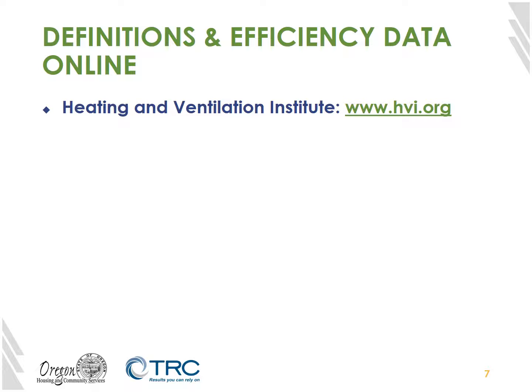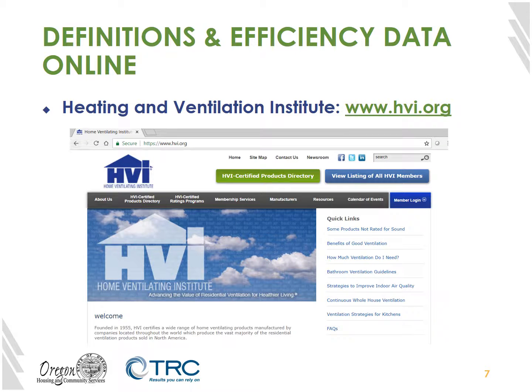We can look at some more definitions and some efficiency data online. The Home Ventilating Institute, also known as HVI, can be found at www.hvi.org. For those of you that work in HVAC regularly, you're probably familiar with AHRI, which is a product directory for heating systems and cooling systems. HVI works very similarly. It is a product directory for ventilation systems. And you can actually click on this green box that says HVI Certified Products Directory and look at and download specification sheets, and you can find the ASE, the SRE, and the TRE for each different model that's available. We know that some manufacturers make very nice claims about their products, but if they're not listed on HVI, then we have no real way of knowing exactly what it is that they're reporting on. So it's our highest recommendation that any product you purchase actually has a product rating available on HVI.